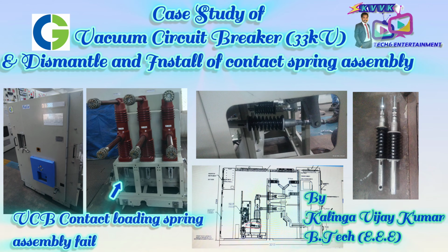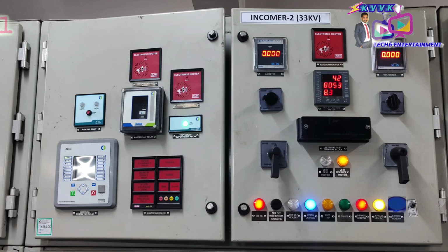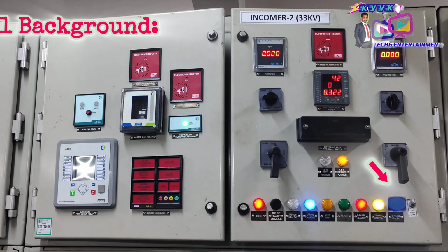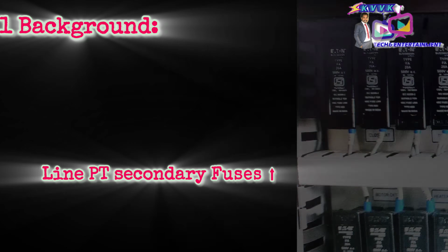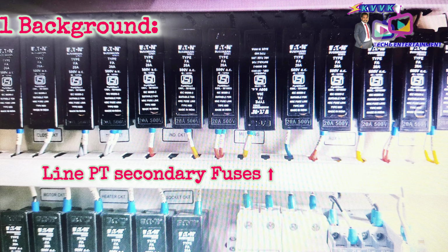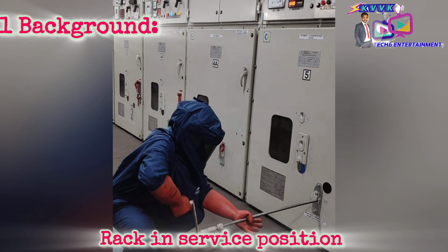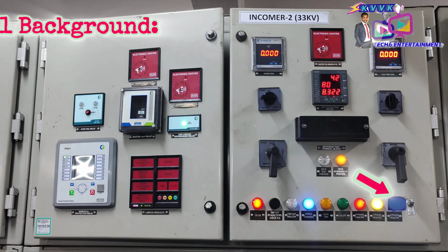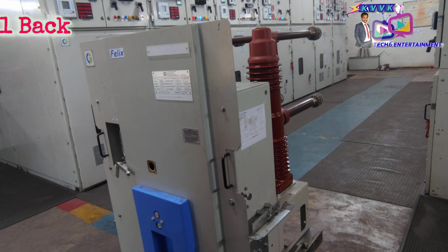In this video, I will show you a case study of a 33 kV vacuum circuit breaker. After completion of preventive maintenance for the 33 kV main VCB, as per regular exercise, we charged the main VCB and found the B phase indication not shown. For background verification, we checked the line PT secondary set fuses and the rack in service position, but the B phase indication was still not shown. So we decided to rack out the VCB from the chamber.